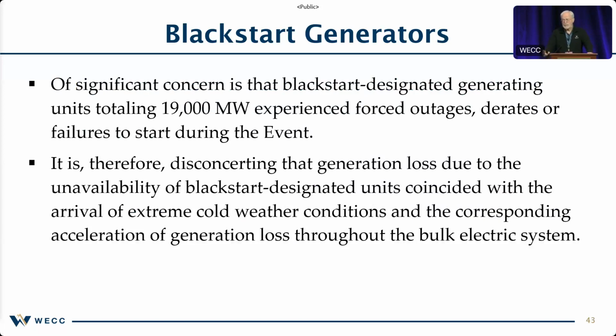In this particular case, 19,000 megawatts of those black start resources were forced outages, derates, or failures to start. And this is in the Eastern Interconnection. They also identified black start generators as being an impact in ERCOT. And one of the things that ERCOT then did after the 2021 event is they did a survey or an investigation into the black start. Why did they trip? Why weren't they there when we needed them? Because if you black out and you don't have the generators that you're depending on to restart your system, then you're in an even worse place than with just a blackout itself.